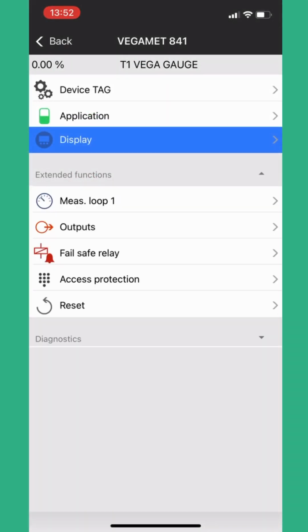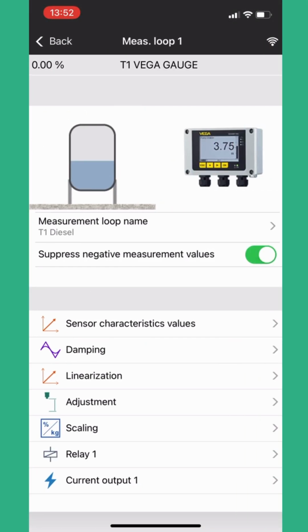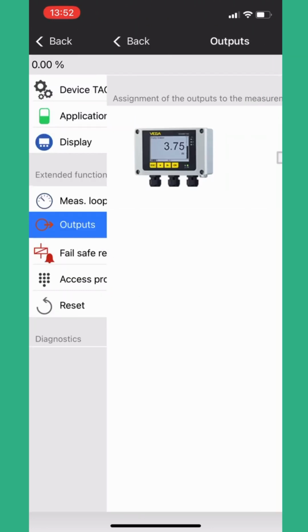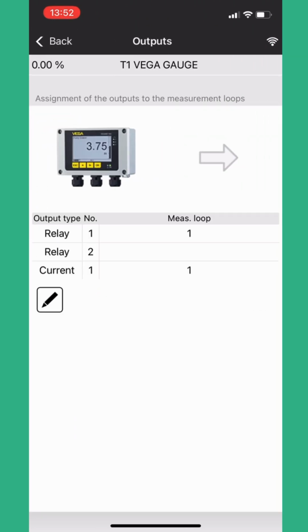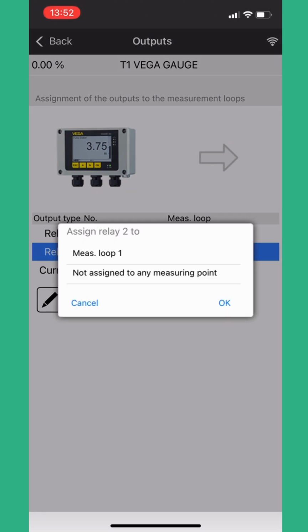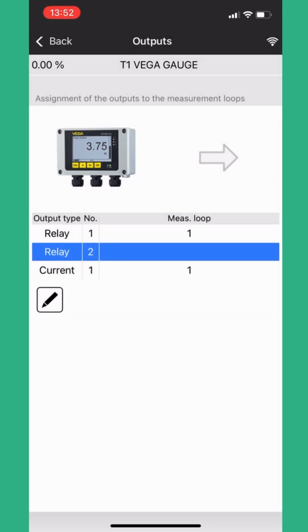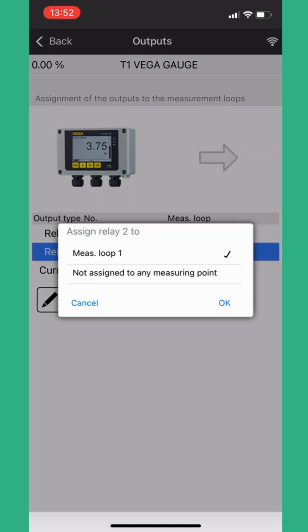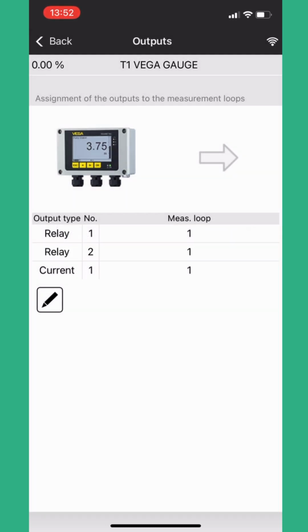In this video, we'll look at the extended functions on the VEGAMET. In this case, we're going to now set up and adjust the outputs for our measuring loop. So we're going to assign relay 2 and relay 1 to measuring loop 1, as well as assign the current output on this device to measuring loop 1.